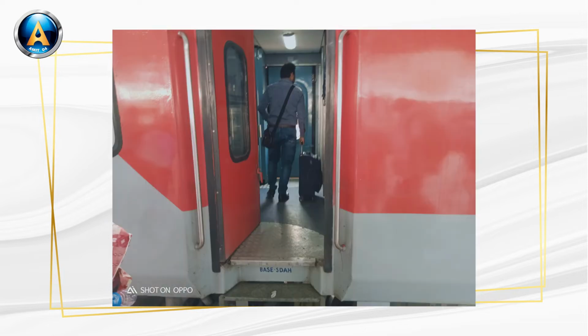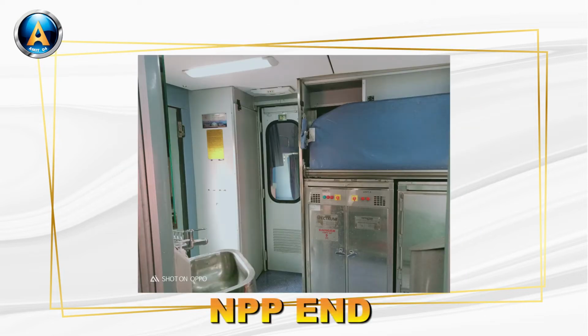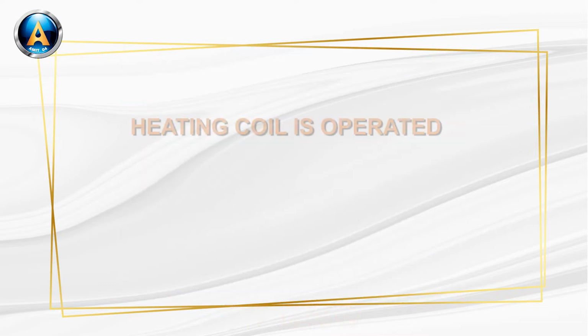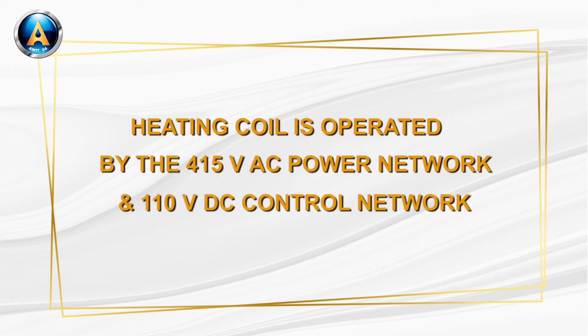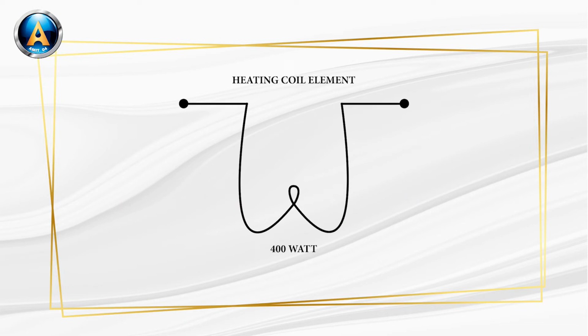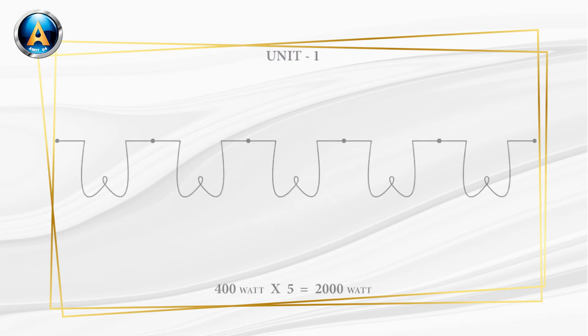And there is a heating coil at each end of every AC coach. The heating coil of the NPP or non-power plant end and the power plant end are both operated by this separate 415 volt AC network and 110 volt DC control network. There is a heating coil element having capacity 400 watt. And 5 elements are connected in series like this to create a unit, and the capacity of that unit is 400 watt into 5 is equal to 2000 watt, that means 2 kilowatt.